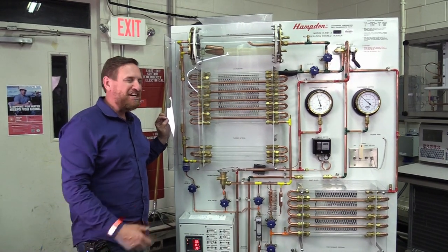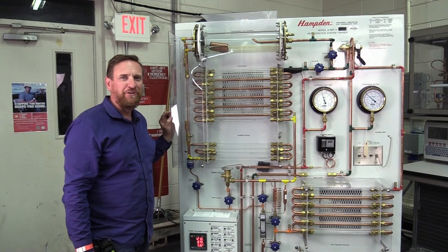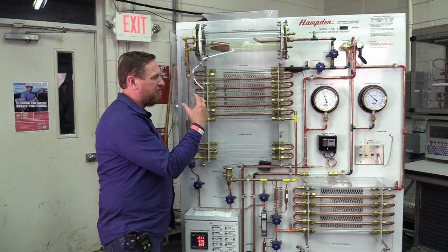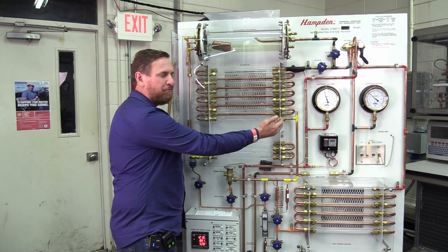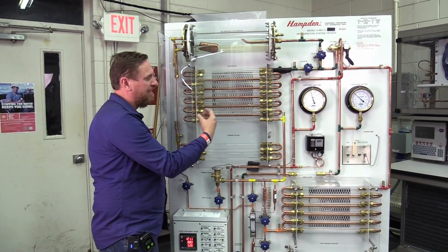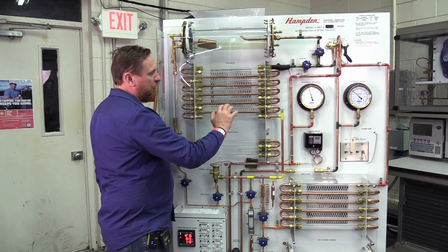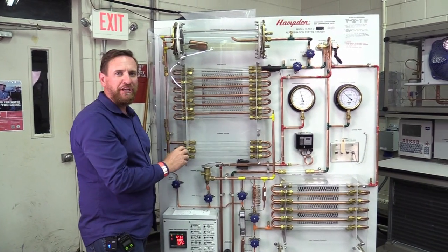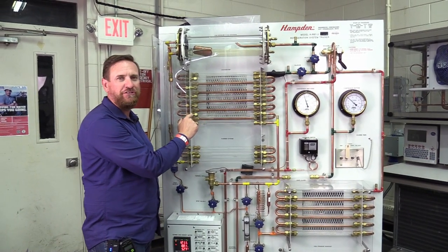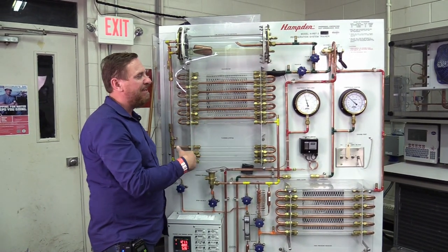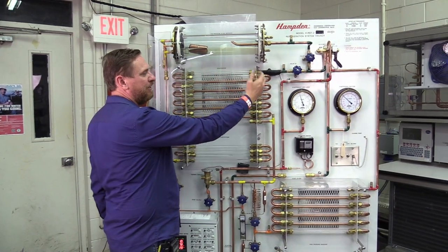Here we have this beautiful opportunity to actually see refrigerant flowing through an evaporator coil. What I love about this system is you can actually see it happening — you see it changing state. So here we're leaving our metering device, going through this evaporator coil at a saturated state, meaning liquid and vapor. As we flow through this evaporator coil, the refrigerant's boiling away. We have to have the fan moving air across this coil to boil the refrigerant. If we stop the fan, we stop boiling refrigerant and then we end up with a flooded compressor.